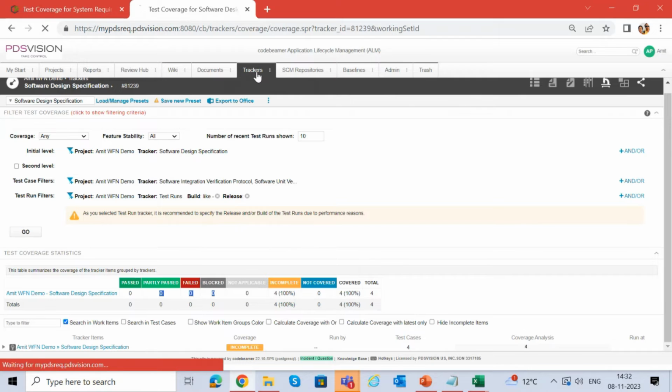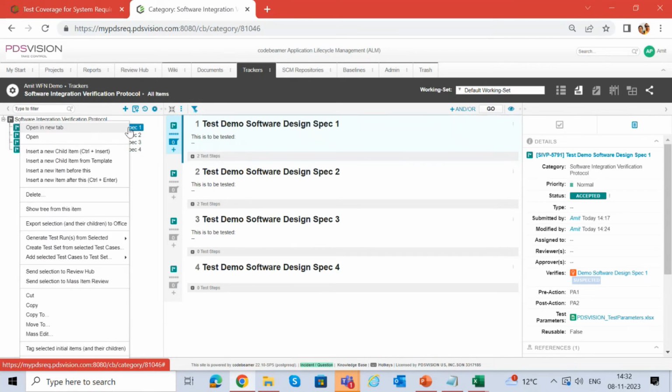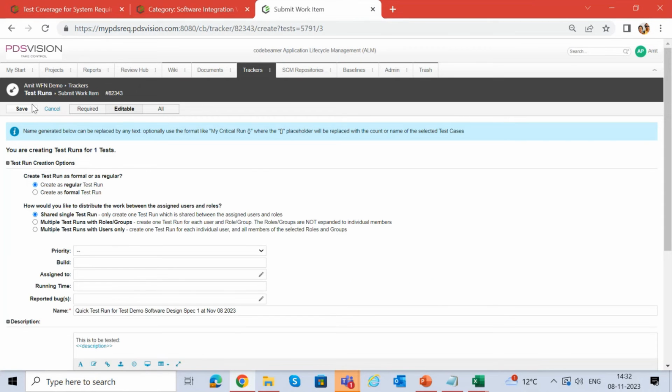Okay. Now I go back and I go to the test. The easiest way would be that I go here, software integration and validation protocol, integration verification protocol. Now for each one, I create a test run and then run. Therefore, first one, I click here and create a test run.